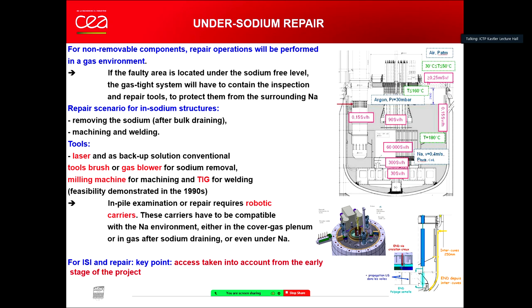a methodology to be able to have inspection everywhere. And why I say that is because sometimes we have also developed a technology in order to clean up the surface below the level of sodium. We did that for the intermediate heat exchanger of Superphenix. There was what we call a bell. We emptied the sodium inside and we repaired the intermediate heat exchanger somewhere.